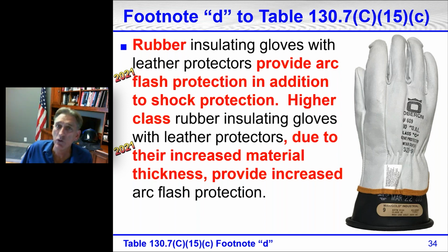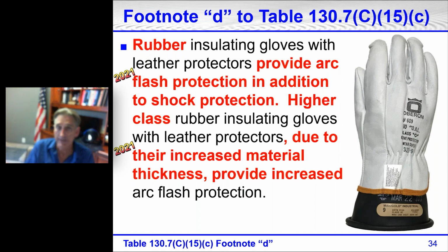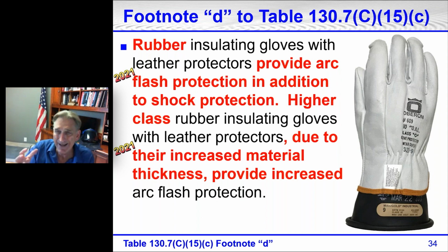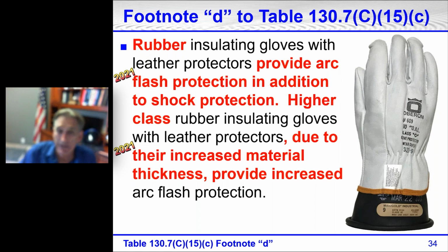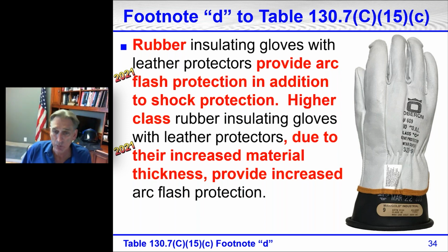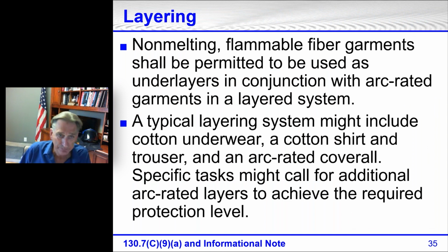So if you're wearing rubber insulating gloves with leather protectors, you do not have to wear arc rated gloves. Now there are arc rated gloves out there, but you don't have to wear an arc rated glove over a rubber glove. The rubber glove with the leather protectors protects against arc flash as well, and there's no arc rating on gloves like this. Layering: non-melting flammable fiber garments are permitted to be used as underlayers in conjunction with an arc rated garment in a layered system. A typical layering system might include cotton underwear, cotton shirt, trouser, and arc-rated coverall. Specific tasks might call for additional arc-rated layers to achieve the required protection. This is an informational note under 130.7(C)(9)(a).